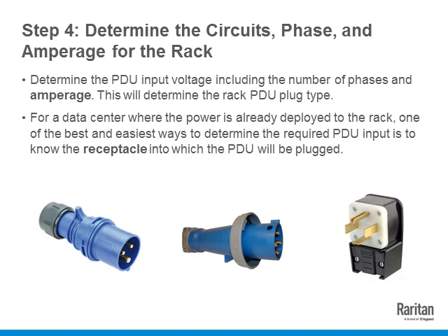Now we have seen the inlet side from an electrical standpoint, and the capacity needed from the load standpoint. Now, how do you bring them together? You have several options to provide the right kind of circuits and phases at the rack level. And everything is dictated by the first choice you made on the kind of voltage that you have in the data center. The plug types vary.